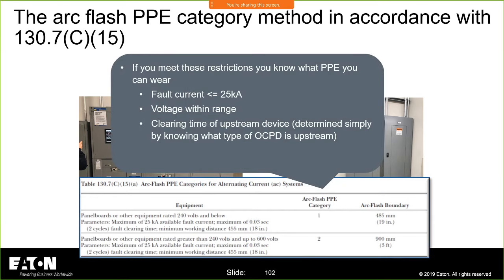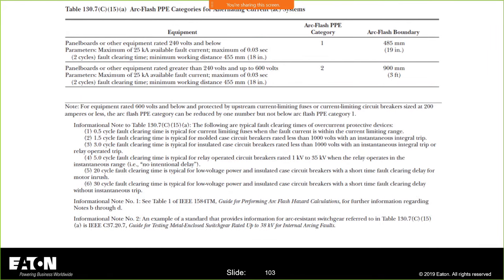As long as I meet those restrictions, and then to know the clearing time, the new informational note they put in this version of 70E tells us that you get a half cycle fault clearing time for current limiting fuses. Now, this says when the current is in the current limiting region of that fuse. Well, I could say the same thing as long as my current is in the instantaneous region of my breakers. I'm in a 1.5 cycle clearing time for molded case circuit breakers. Insulated case is 3 cycle fault clearing time. Right? Power circuit breakers, you're moving up to 5 cycles, 20 cycles, 30 cycles. So what I do know when I'm looking at this table is anything that's 2 cycles, I'm in a 1 or a 2 PPE category. It's nice and easy.